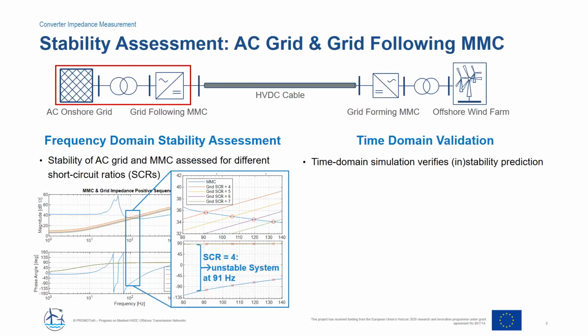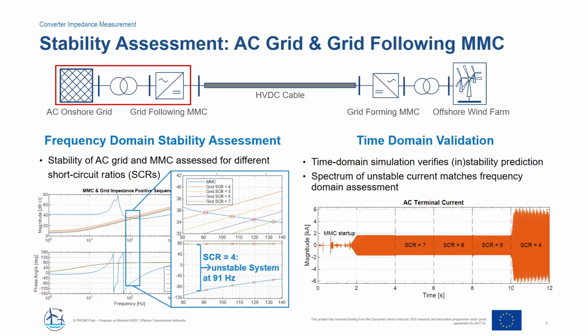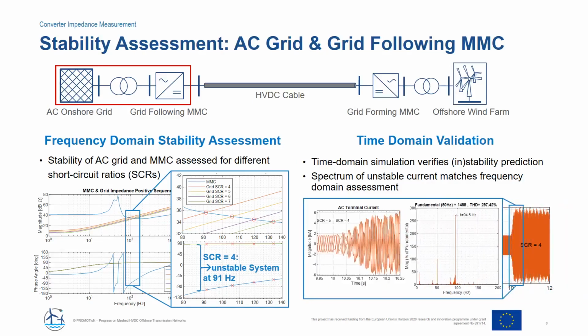Here we show the time domain validation of this. You can see this is the spectrum. We do the simulation, and then we continuously, step by step, reduce the SCR of the AC grid. We see that when changing from 5 to 4, this oscillation happened. You can see it a bit more clearly in this diagram. You can see the oscillation, and also the frequency domain analysis, which clearly shows this oscillation happened at 94.5, close to 100 Hertz.